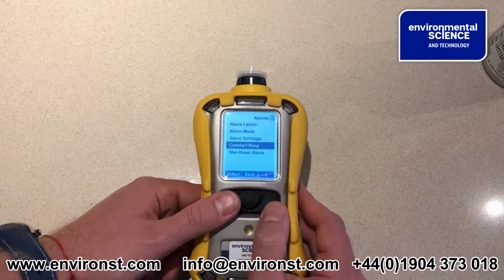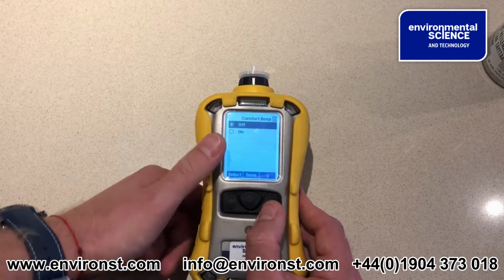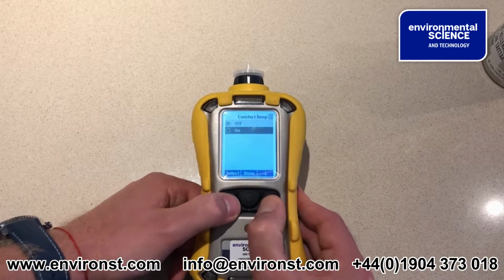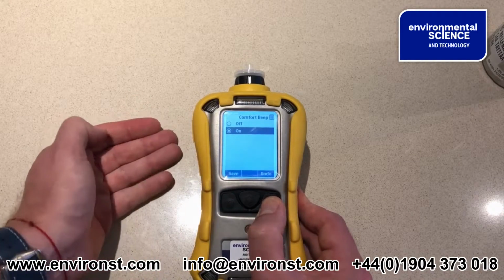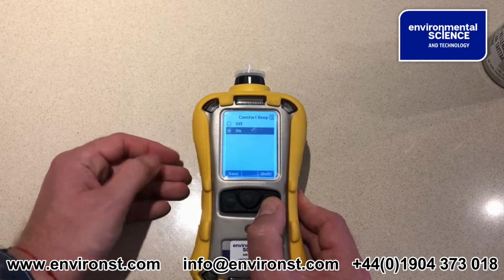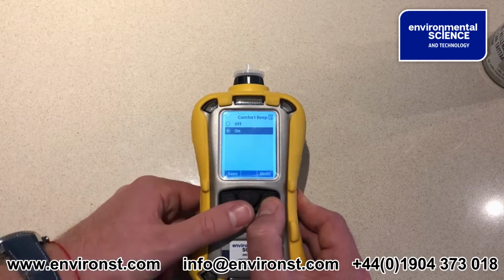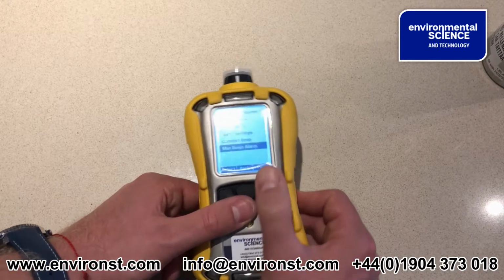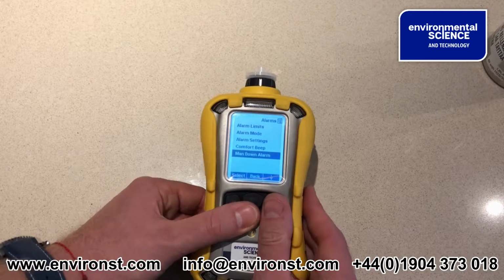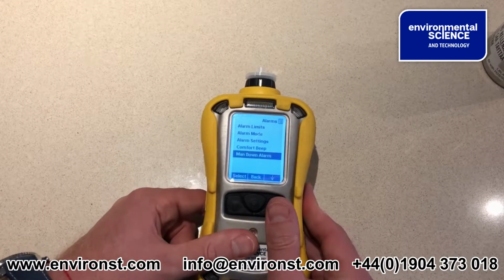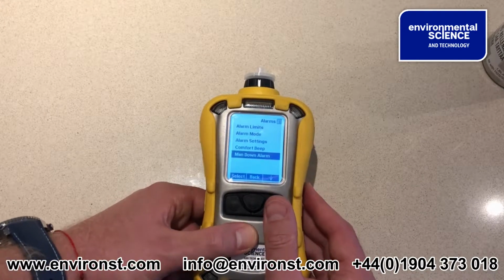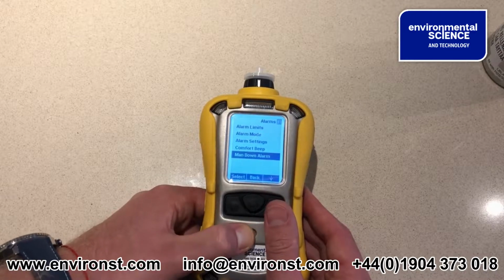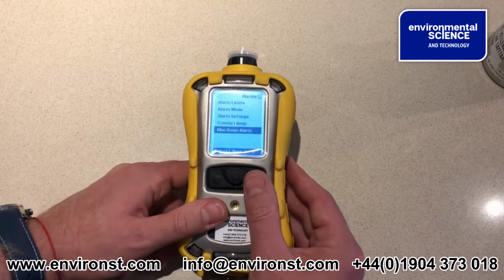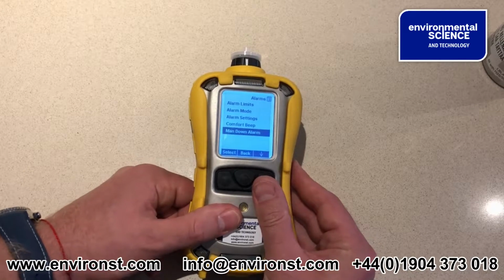Comfort beep. Now this is essentially, if we go into it, we turn it on, and the unit will beep periodically just to let us know that it's still working and okay. We're going to ignore that. And man down alarm is essentially, there's a little accelerometer in here. If the unit were to be still for too long a period, it would go into a man down alarm, assuming that someone's not responding or just not moving, and that's a problem.